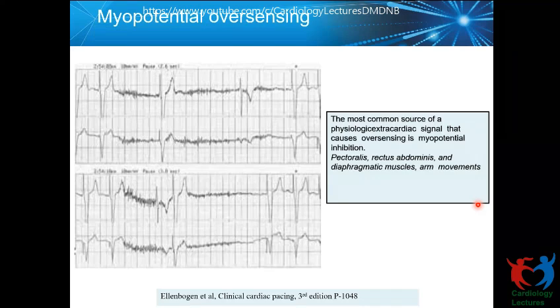That's the electromagnetic interference. And then this is an example of a myopotential oversensing, which is picked up from the Ellenbogen book, which is very typical of a unipolar system. You don't see that in a bipolar system because the CAN is not acting as an electrode. So typically this myopotential comes from the pectoral muscle in a unipolar system. You can recognize the difference between electromagnetic interference and the myopotential. Very, very rarely in a bipolar system, it picks up the diaphragmatic myopotential, which is extremely rare, which can be managed by reducing sensitivity.